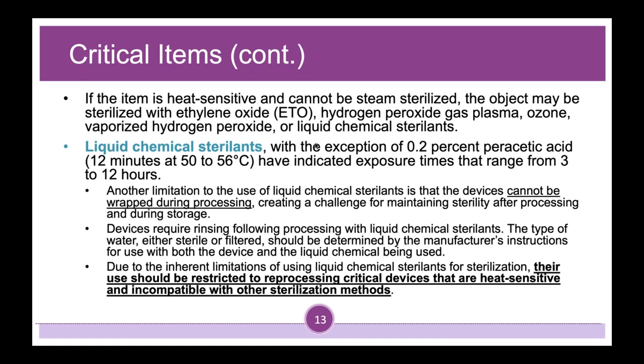If the item is heat sensitive and cannot be steam sterilized, the object may be sterilized with ethylene oxide, which has lots of issues, hydrogen peroxide gas plasma, ozone, vaporized hydrogen peroxide, or liquid chemical sterilants. Liquid chemical sterilants, with the exception of 0.2% peracetic acid, have indicated exposure times that range from 3 to 12 hours.